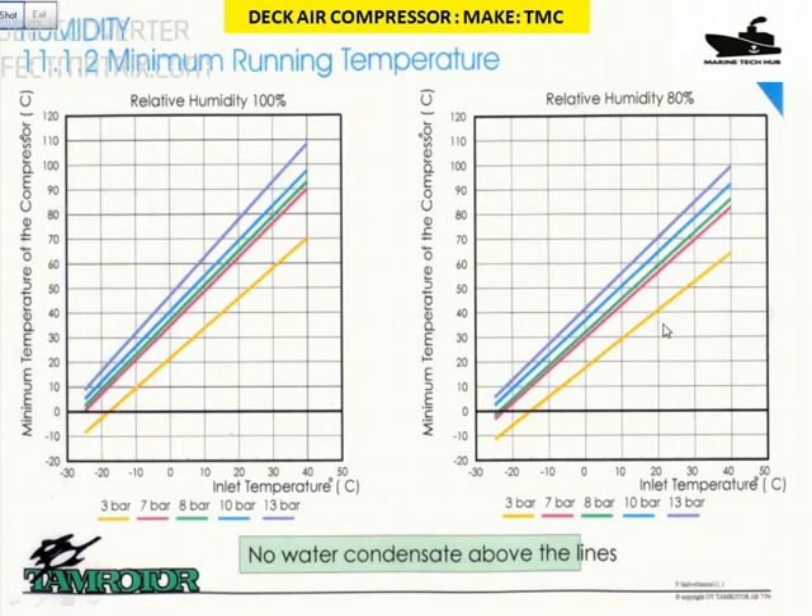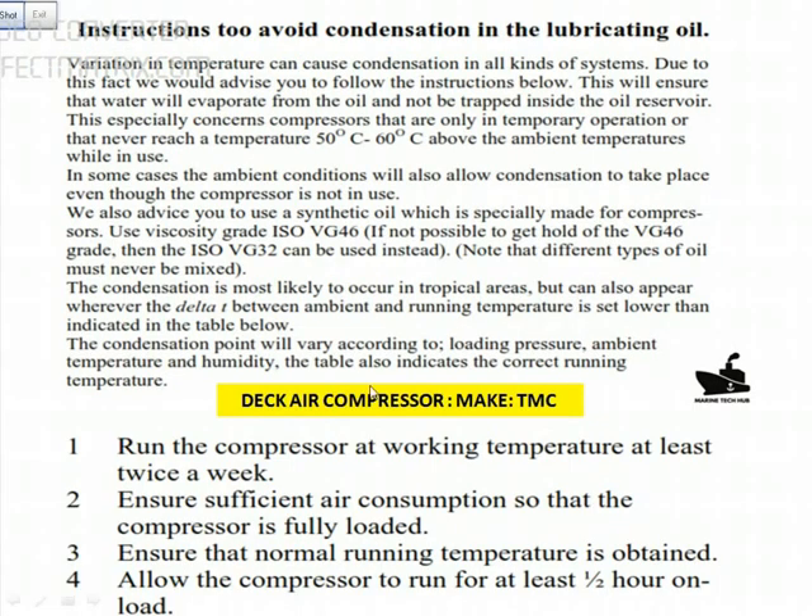You have to change the oil regularly if you are not maintaining the temperature. The important thing to note is you need to run the compressor at least twice a week. If you are not using a TMC compressor, run it at full load for at least half an hour. If you don't, condensation will take place and you will spend a lot of money on maintenance of the Deck Air compressor. Please remember these points for safe running and to save money and time for the company.